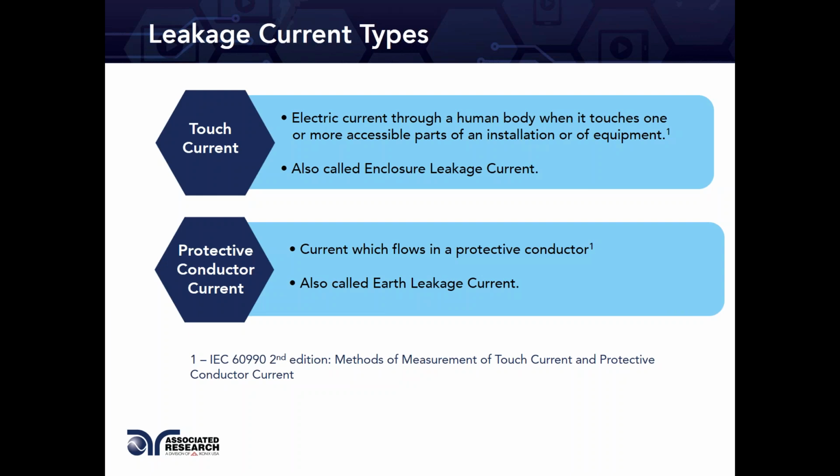So now what we need to keep in mind is that some standards are pretty heavily involved with leakage current tests, while others are not. A good example of a test standard that involves the leakage current test pretty heavily is the medical standard, the IEC 60601-1 3rd edition. So we're going to look at some examples from that, and just keep that standard in mind when we look through some of the medical measuring devices and some of the videos that we're going to show you.